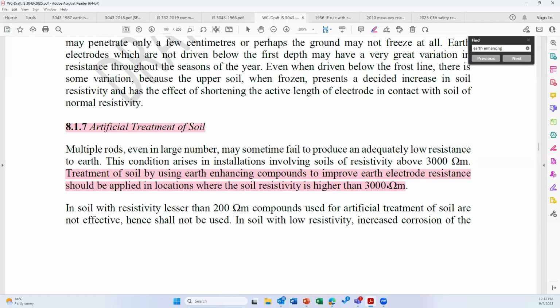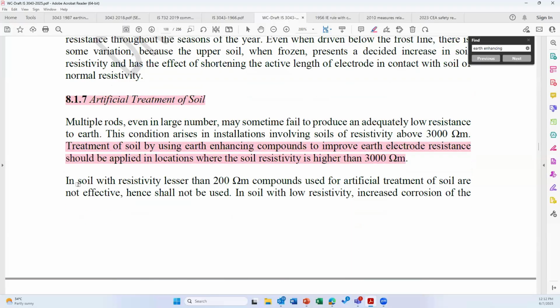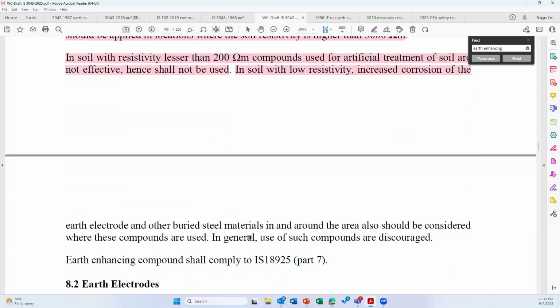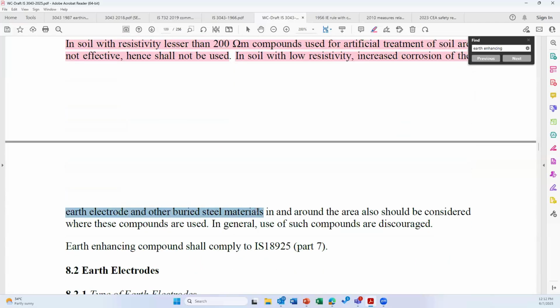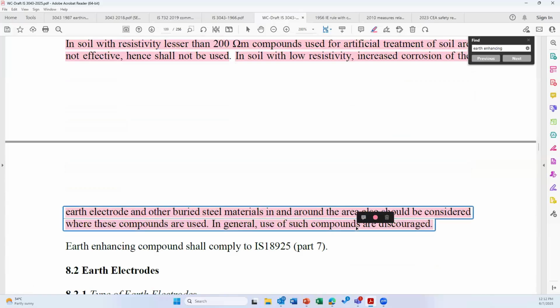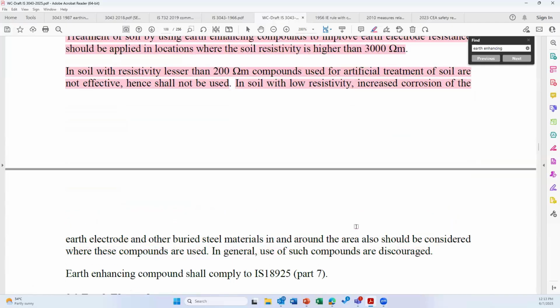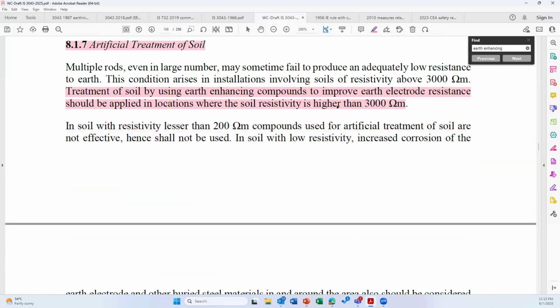That means if the soil resistivity is lower than 3000 ohm meter, you should not use earth enhancing compound, because in soil with resistivity lesser than 200 ohm meter, compounds used for artificial treatment of soil are not effective, hence shall not be used. In soil with low resistivity, increased corrosion of earth electrode and other buried steel metal in and around the area should be considered where these compounds are used. In general, use of such compounds are discouraged. So basically, we are not supposed to use this earth enhancing compound or this particular chemical.